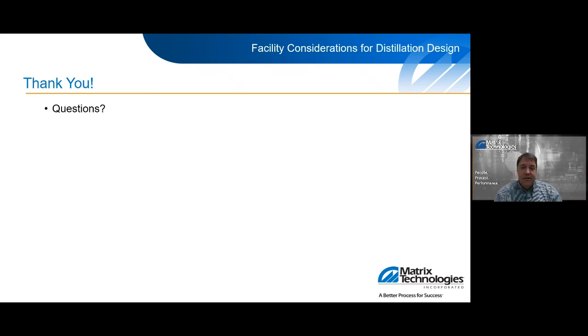But then there's also the situation of the emergency venting, where if there is a fire in the area and contents within the tank start to vaporize and increase the pressure, then there needs to be an emergency vent as well to basically pop off and vent to atmosphere, to control the situation. So there's a twofold thing. One's simple breathing with a flame arrestor, but then there's also the fire case, which takes precedence.